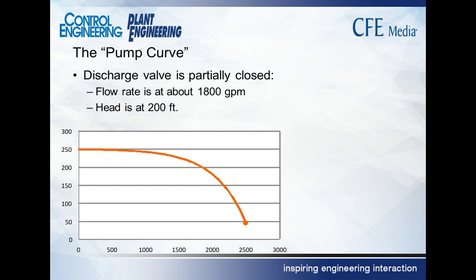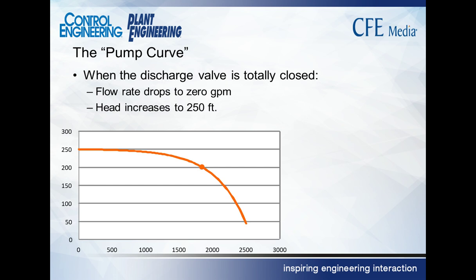So if I got this pump and I close the discharge valve down, I could adjust the flow to, say, 1,800 gallons per minute, and at that point I'd have 200 feet of head. Does everyone see the operating point is about 1,800 gallons per minute and about 200 feet of head? If I continue to close down the discharge valve, I can actually shut down the flow of the pump completely and have zero flow. We refer to this as dead-headed. Now the pump is still running, but there's no flow through it.